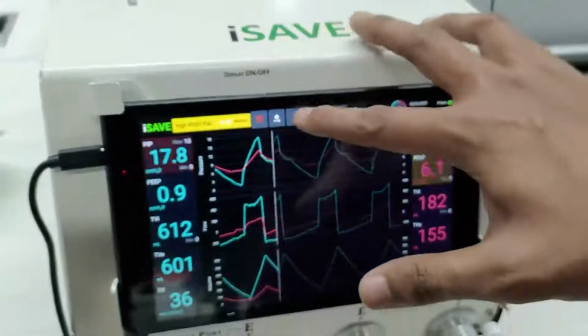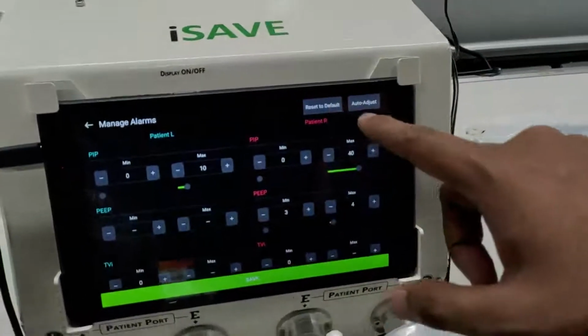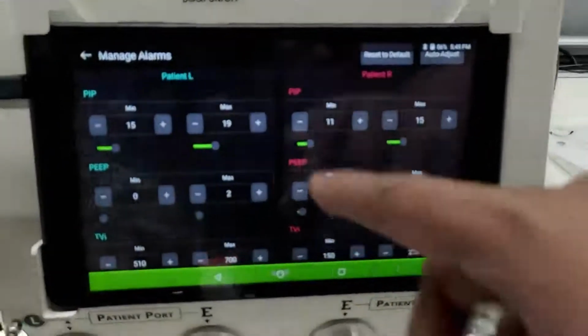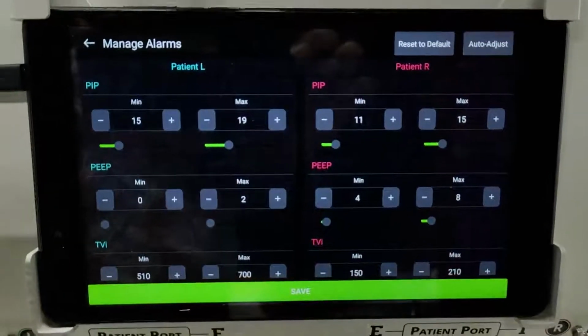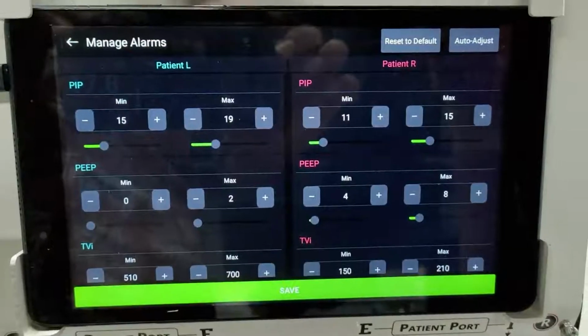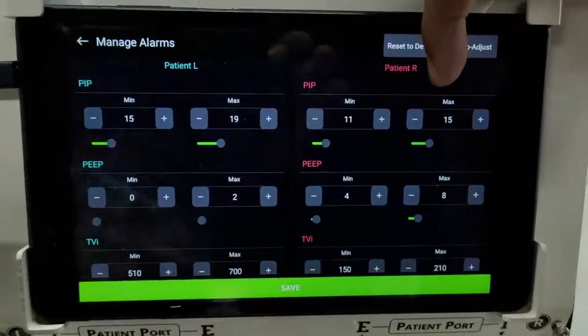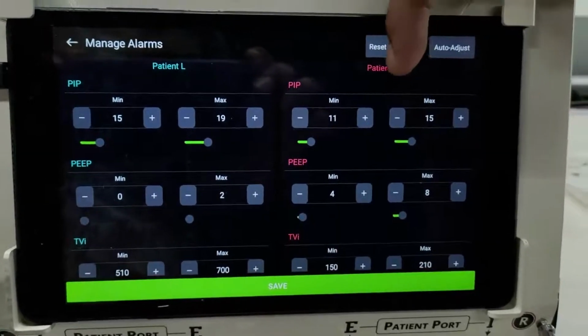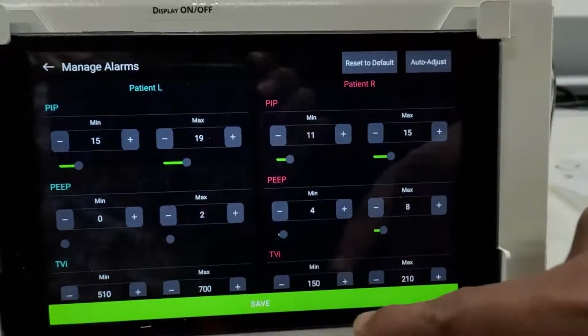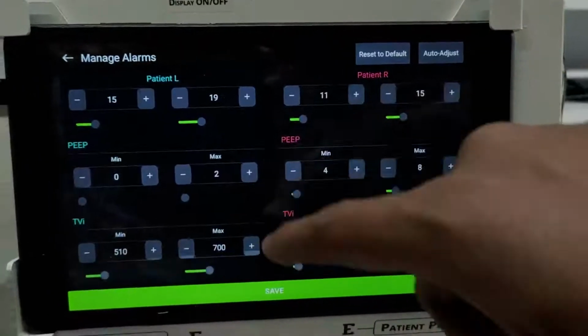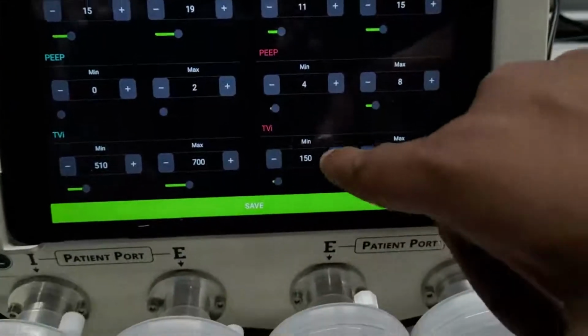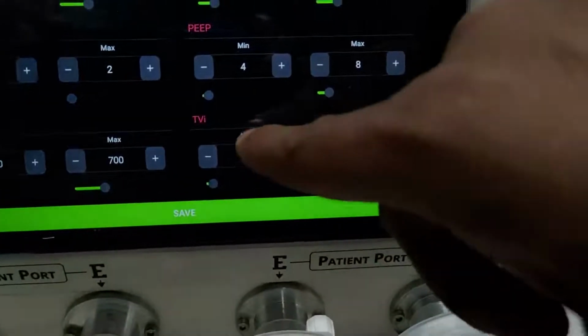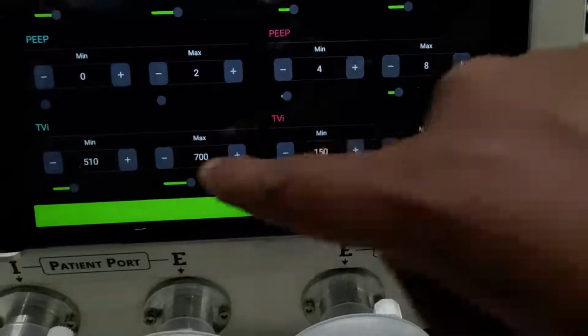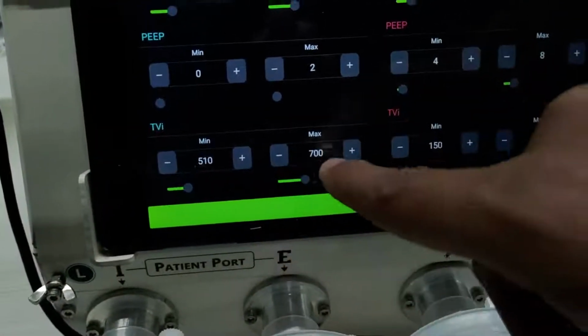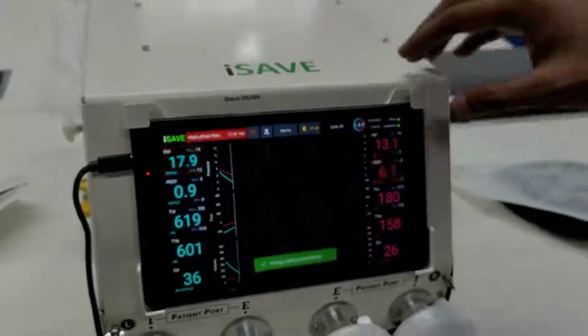So let's go back, let's reset our alarms. So let's use auto adjust. Auto adjust is a nice feature where it'll auto set the min and max values for each of these alarms, and that way we have a comfortable margin in which the errors can occur. So you can see that since I've adjusted the valve on the right side, my min and max values for patient R tidal volume is 150 to 210, whereas left side is 510 to 700. Let's save that.